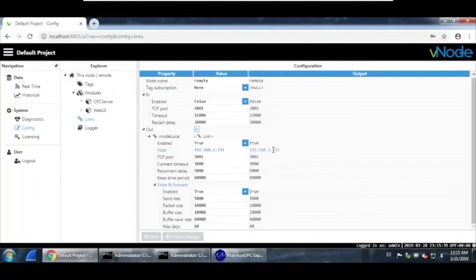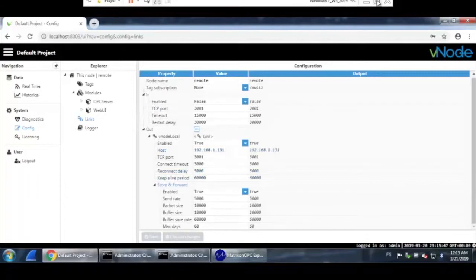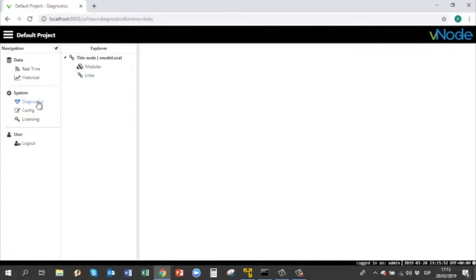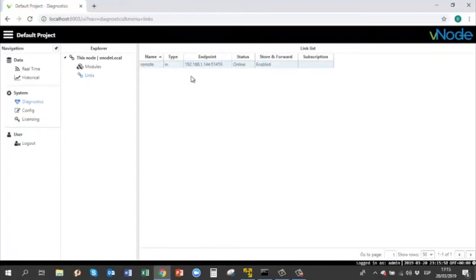After setting this up, we have configured the link from Vnode local to Vnode remote and enabled the store and forward feature. The next step is to test if the connection between both Vnodes is working. Let's go to Vnode local. Under diagnostics, under links, you will see a connection already created from the endpoint for this IP address — which belongs to Vnode remote — along with the port. It says store and forward is enabled and the status is online.